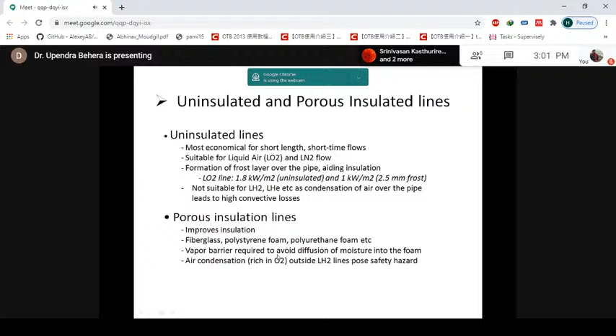Then porous insulation lines have slightly improved insulation compared to the uninsulated one; fiberglass, polystyrene or polyurethane foams are used. But once they cool down, there is a chance that air and moisture get in, and this moisture gets condensed there, which is a safety hazard for hydrogen use. So for that you need a vapor barrier to avoid the diffusion of moisture into this type of insulation.